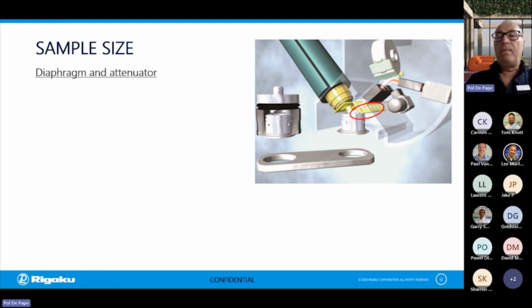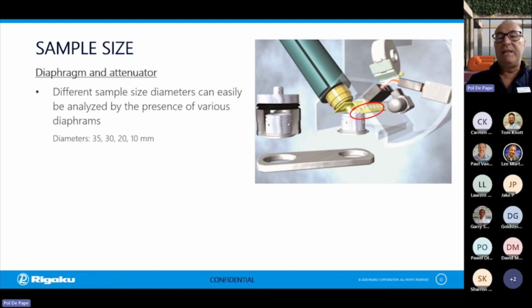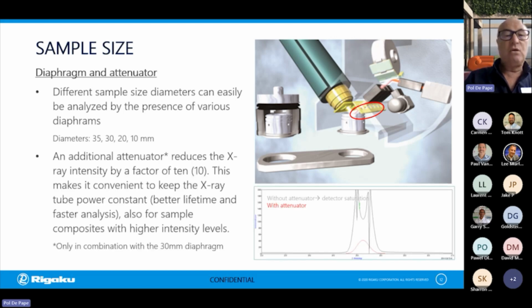So after the sample, we have diaphragms and also an attenuator. So we have 4 sample masks, which go from 35 to 10 millimeter. And we have also one attenuator. And what is now the advantage of this attenuator? So we ideally want to use our X-ray tube always on the same power. This is the ideal. But sometimes, of course, we have samples that contain one element or 2 elements that have a higher concentration. Thinking, for example, about iron ores or steels, which have a high amount of iron, maybe chromium, nickel. So we can use this attenuator to reduce the intensities.